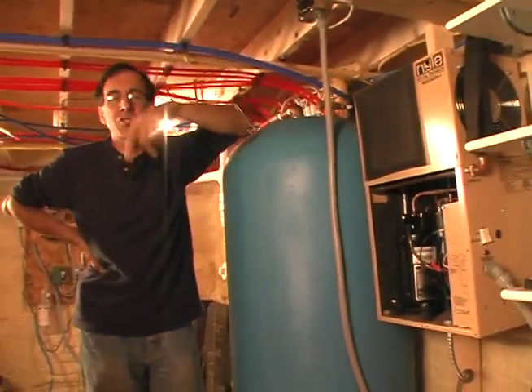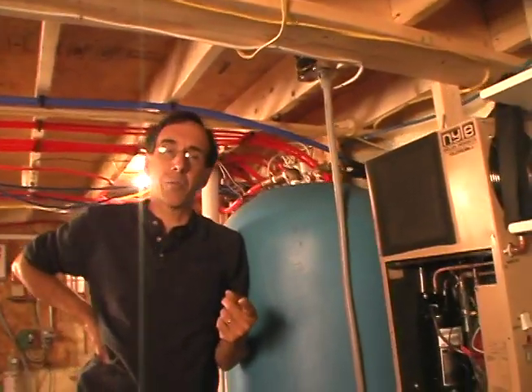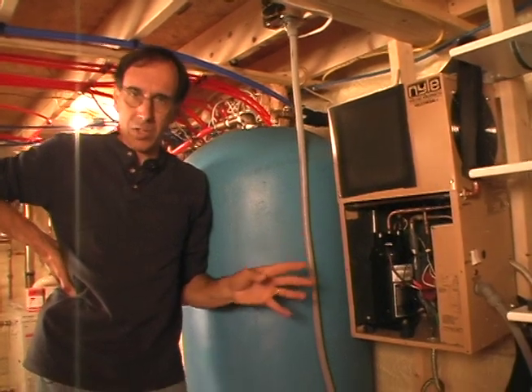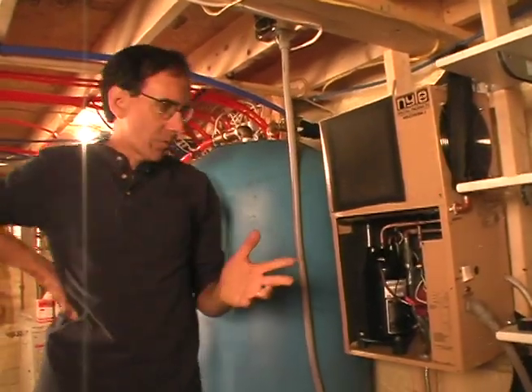There you go, we got the light going. That's a bronze circulator pump. We don't use iron or steel pumps in potable water systems because they will rust. Potable water being water that would come out of your tap, there's a lot of oxygen in it, so you have to use something non-corrosive. In this case, a bronze circulator pump is a standard industry item.